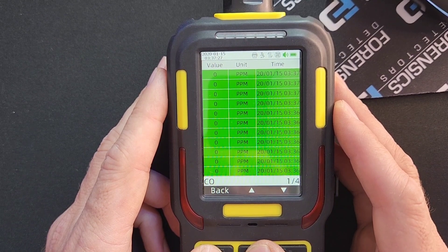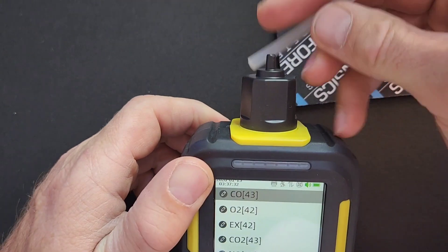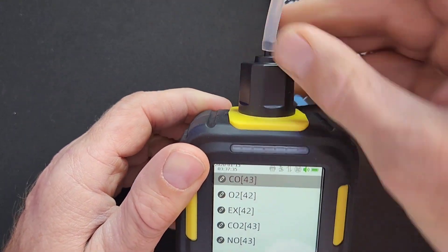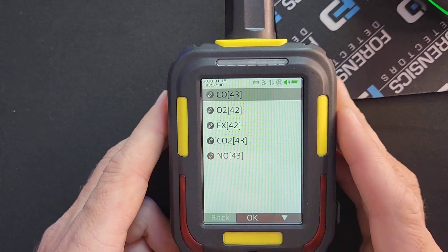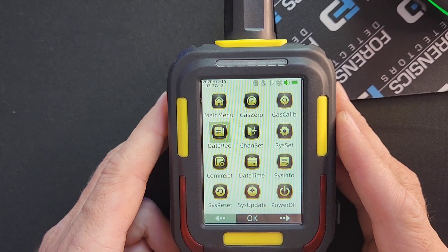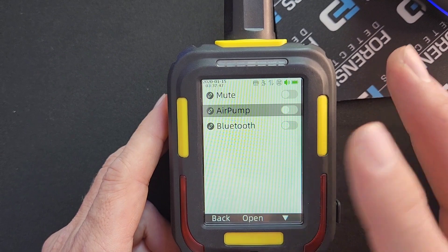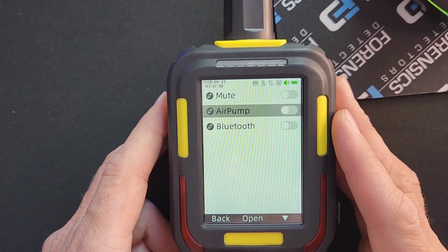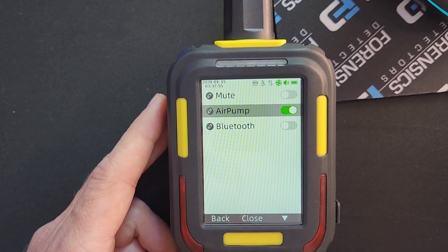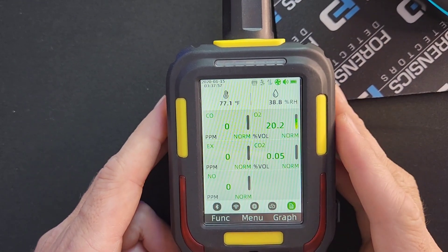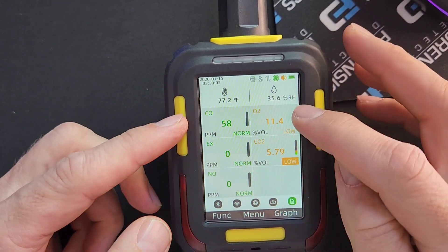I'm going to plug tubing in and take a sample of gas, then step through the recording. It's still recording — I'm going to turn on the pump. By the way, pump on or pump off, it still records. I'll turn on the pump, turn on the gas, and it is now taking in the gas. You can see the numbers going up — I'm taking in carbon monoxide, reducing O2, and increasing CO2.